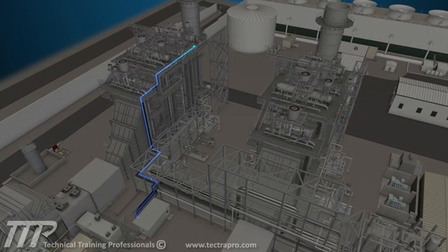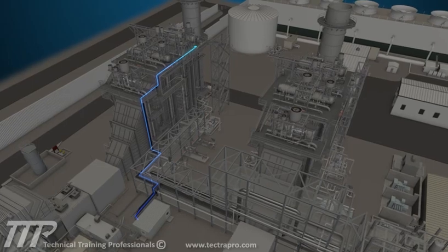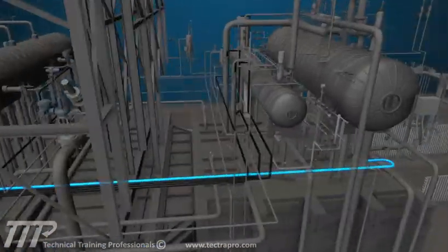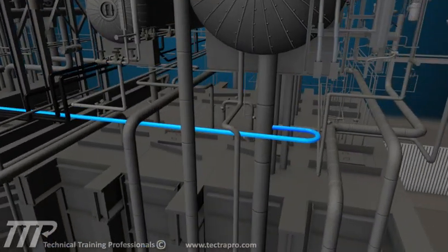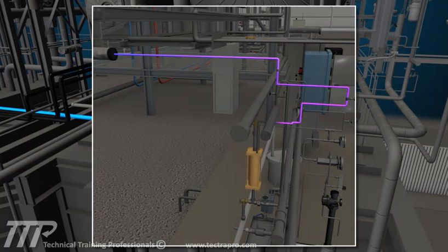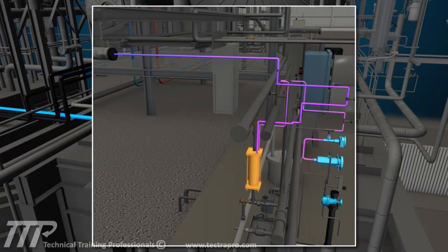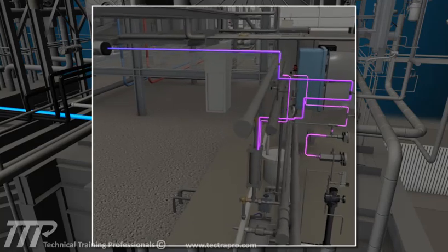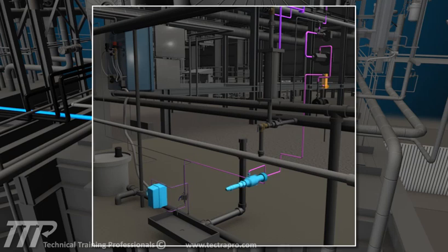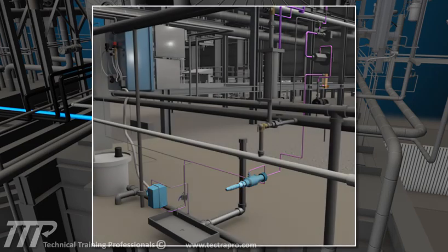Sample points 3 and 4 are the boiler feed pump suction 1 and 2. These sample points provide a means to monitor the condition of the water leaving the low-pressure HRSG drum before delivery to the intermediate and high-pressure HRSG drums. At the sample panel, the feed water is cooled and its pressure is adjusted. Flow is adjusted just upstream of the pH analyzer and the specific conductivity analyzer. Provisions for manual sampling are available to further analyze the condition of the water.